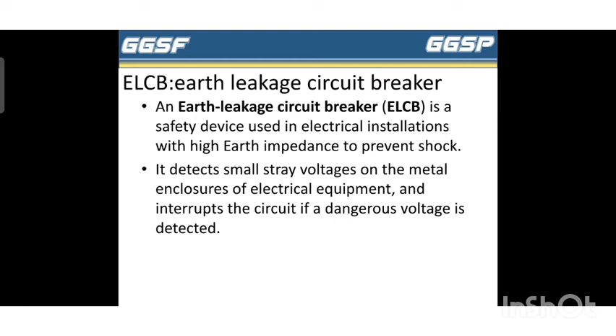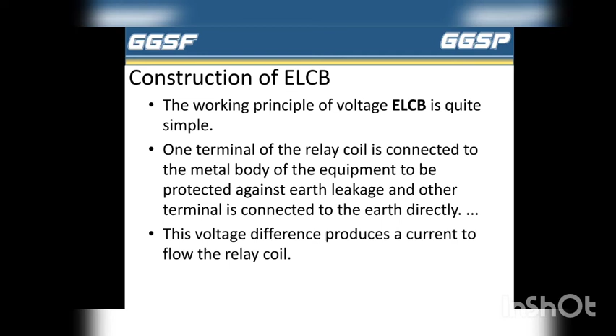Now, first one is construction of ELCB. The working principle of voltage ELCB is quite simple. One terminal of the relay coil is connected to the metal body of the equipment to be protected against earth leakage, and the other terminal is connected to the earth directly. This voltage difference produces a current to flow through the relay coil.